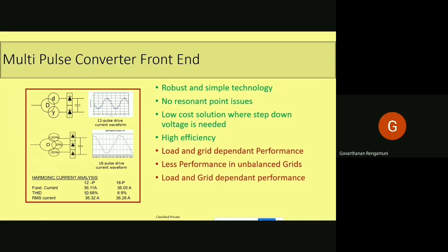The fourth technique to meet IEEE 519 is to use a multipulse converter. This is a traditional technique. So you might have learnt about the 12 pulse transformers and 18 pulse transformers. 12 pulse transformer, in the sense, there will be two rectifiers. They will be connected in parallel. One rectifier will be connected to a delta secondary winding, and the other rectifier will be connected to the star secondary winding. The voltage from the secondary windings will be displaced by 30-degree angle.